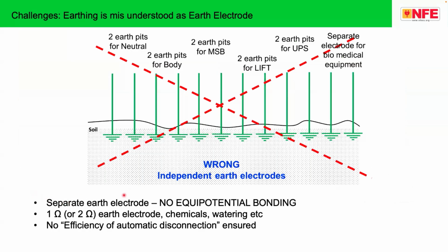One fashionable requirement demanded by the electrical biomedical engineers, and sometimes also by the electrical inspectorates in some of the states, not all the states, is to have a separate earth electrode, separate for neutral, separate for body, separate for equipment, and so on. Please note that earthing has nothing to do with earth electrode. Earthing is about interconnecting all the metal parts in such a way that no shock exists. So in the standard, this cross mark is given to tell users that please don't use it.